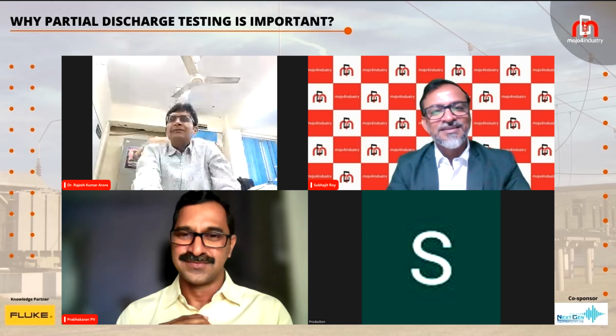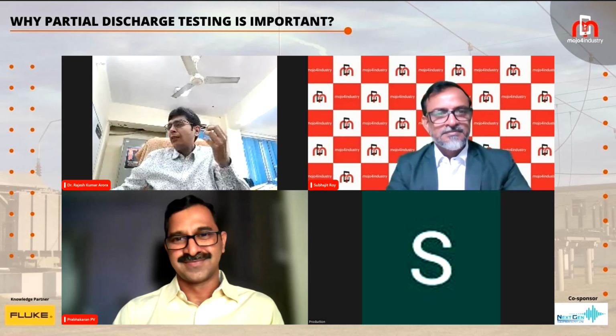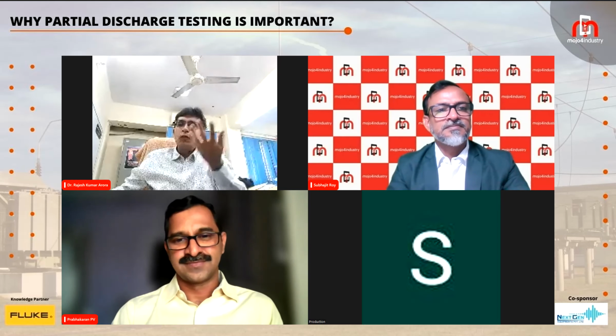Yes, we are maintaining all kinds of equipment like transformers, gas insulated substations, major cables, cable terminations, cable joints, circuit breakers, isolators, disconnectors. As mentioned very well by Prabhakaran sir, it is mandatory to understand the effect of partial discharge. When I say these equipments, there are only 3 types of insulation we can use - liquid transformer oil, SF6 gas, and solid insulation like polystyrene and epoxy, which we use in our systems.